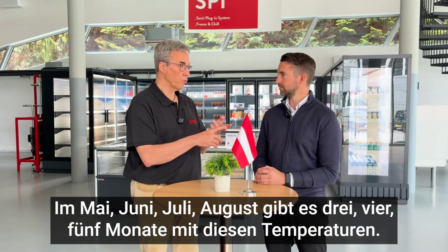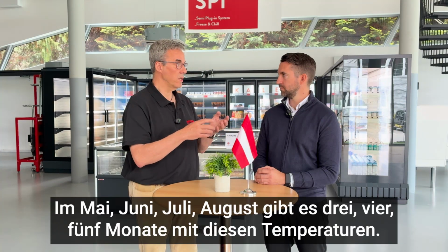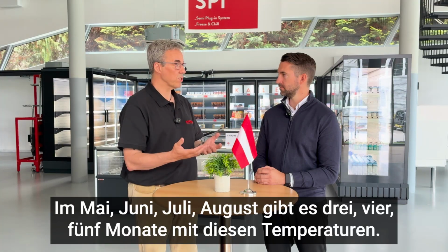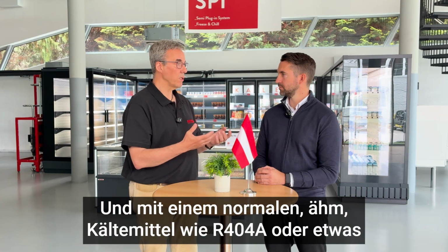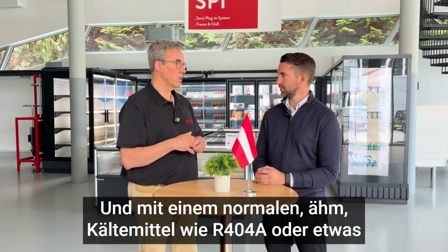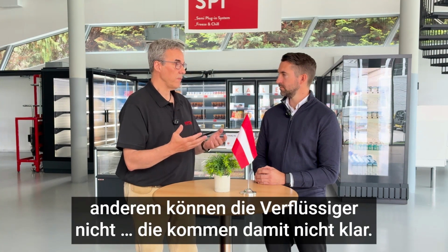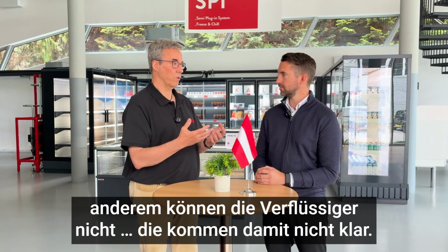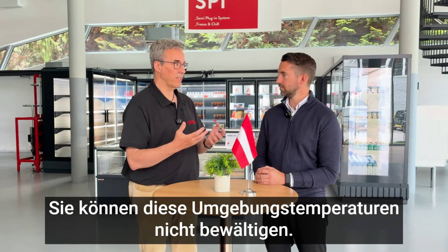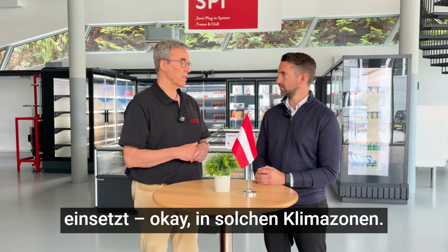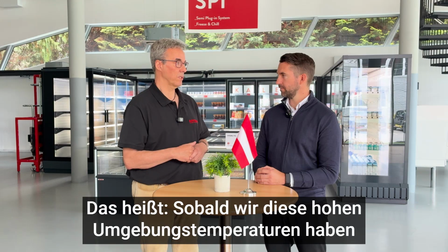In May, June, July, August, there are 3, 4, 5 months with this temperature. And with normal refrigerants like R404A or something else, the condensers cannot work. They cannot handle this ambient temperature. So that's a reason for using CO2 in such southern climate areas.